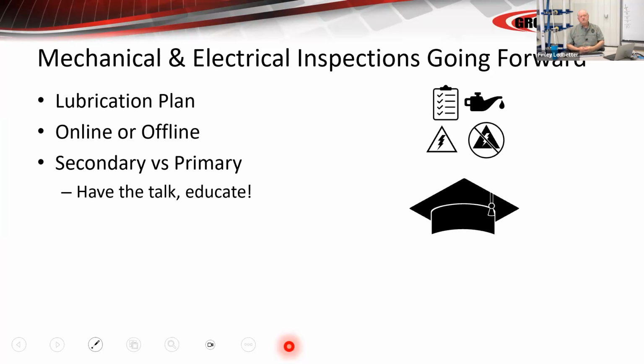So secondary versus primary, I think you have to do a primary test initially. At some point that has to have been done to prove out all the circuitry, to prove out the CTs, or all the plugs plugged up, or all the wires run the proper places. Can you inject a secondary test every cycle or two?